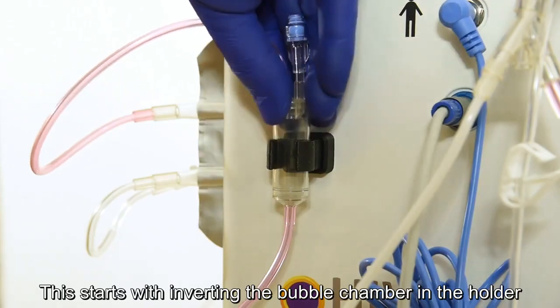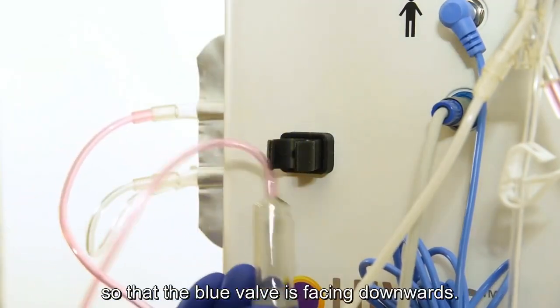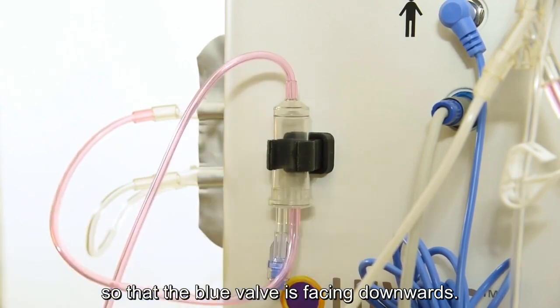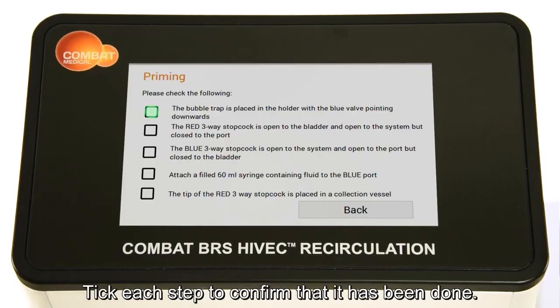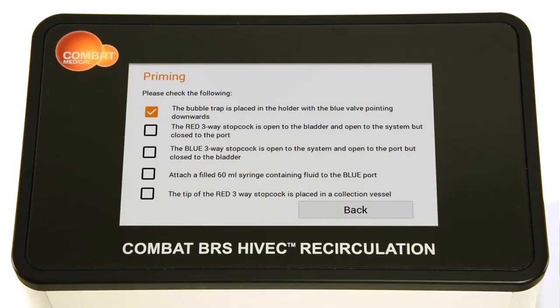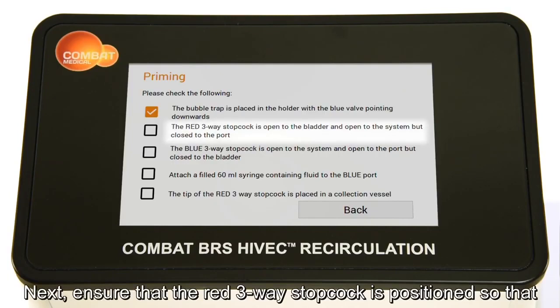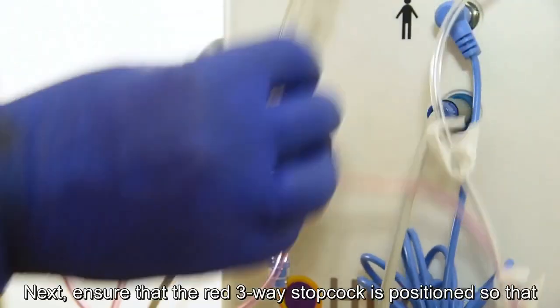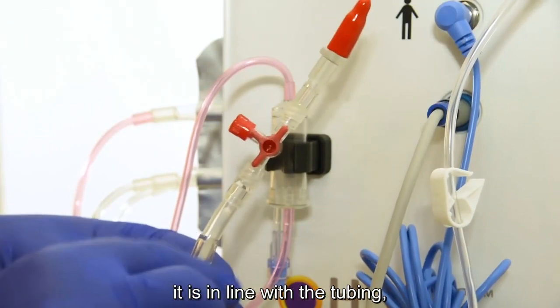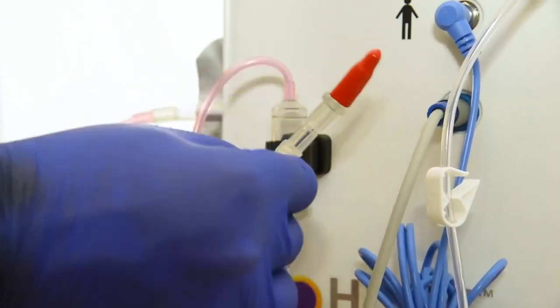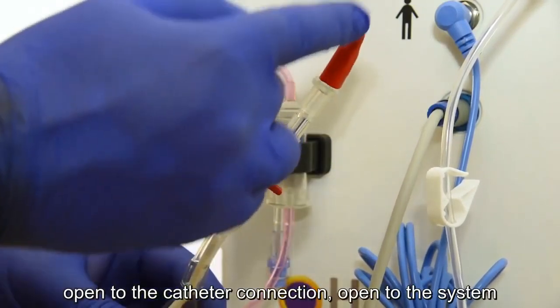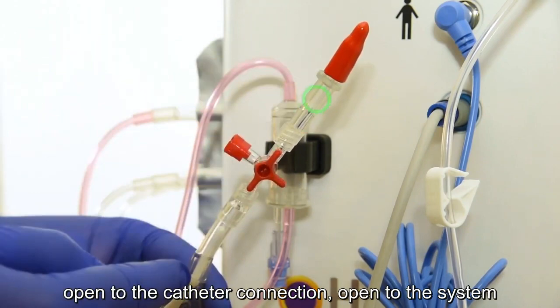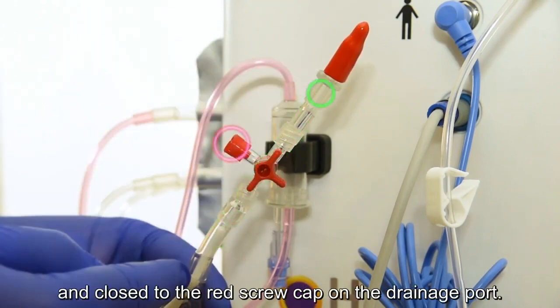This starts with inverting the bubble chamber in the holder so that the blue valve is facing downwards. Tick each step to confirm that it has been done. Next, ensure that the red 3-way stopcock is positioned so that it is in line with the tubing. Open to the catheter connection, open to the system, and closed to the red screw cap on the drainage port.